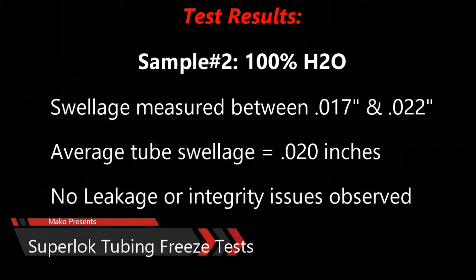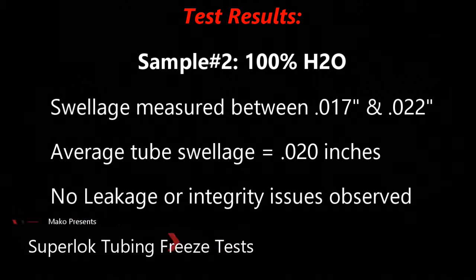In test sample number two filled 100 percent with water, we recorded an average tube swellage of 0.020 inches. There was no leakage or integrity issues observed in the sample.